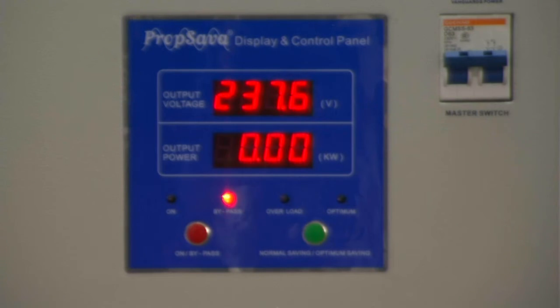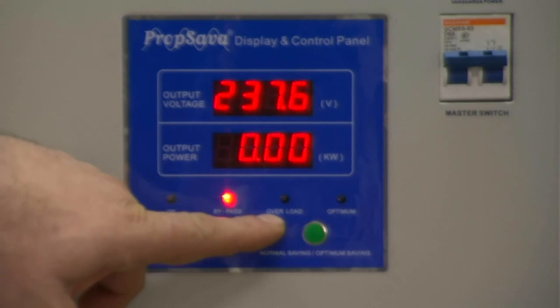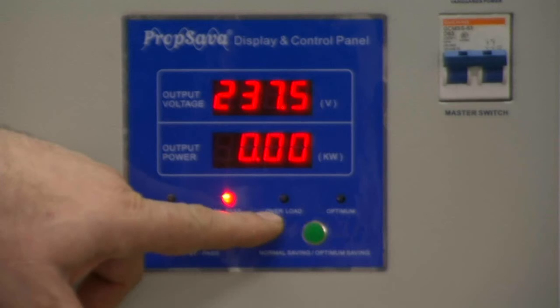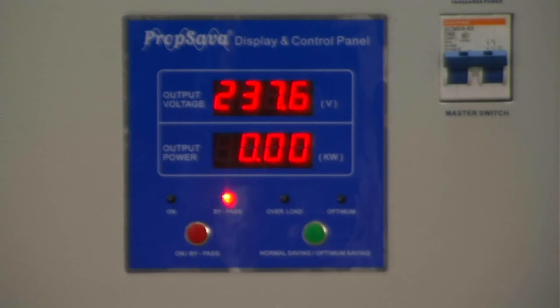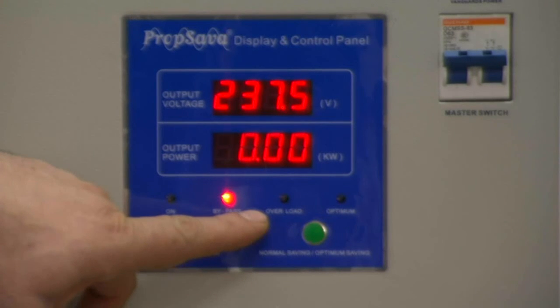PropSava. In the event of any failure of the PropSava, or in the event of the PropSava going outside its normal range, which is plus or minus 10% on the input mains voltage and plus or minus 1% on the output voltage, in those events, the bypass will be automatically engaged. We also have a couple of more LED lights. One here shows overload. If the load on the distribution side is greater than the power size of the PropSava, then the system will go into bypass and this overload light will illuminate.